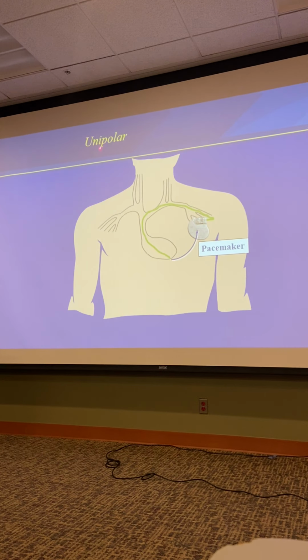You'll see us sometimes refer to unipolar or bipolar pacing. Unipolar pacing means that there's a connection here between the tip of the lead and the can. And the electrical signal goes between the electrical connection here and the can. So it goes through the chest wall. This makes for a very simple lead. These leads are metal and constantly bending with every heartbeat for the rest of the life. So metal, when it bends a lot, can fatigue and break. So these leads are simpler, a single conductor.